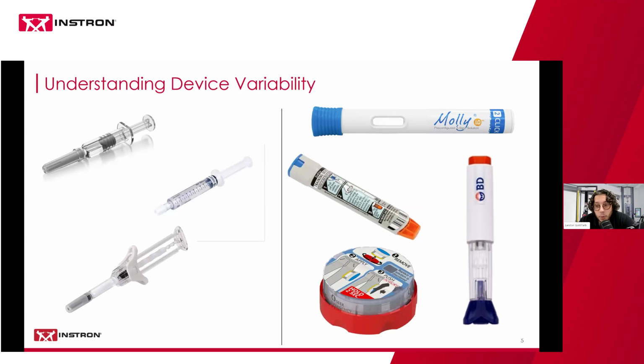The big driving force behind this is auto injectors as a combination product have to serve the specific patient population and indication that they're designed for. And inherently, because these are meant to be delivered by the patient themselves, it's not intended that a physician is performing this procedure. You have to design to the needs of the patient. And that can mean, if you're talking about patient population, could be children. So maybe you need it to be as easy to use as possible. Maybe the patient population has severe arthritis and they can't hold on to a device with a certain form factor. So all of this will inform how the device is designed, and all of those design choices will in turn inform how we need to interact with this device on the system.